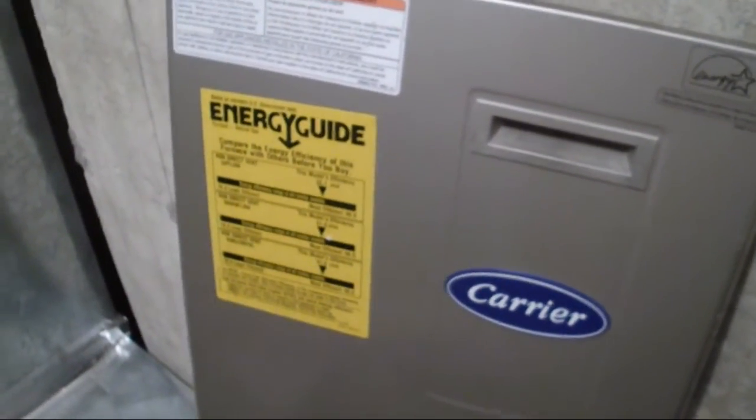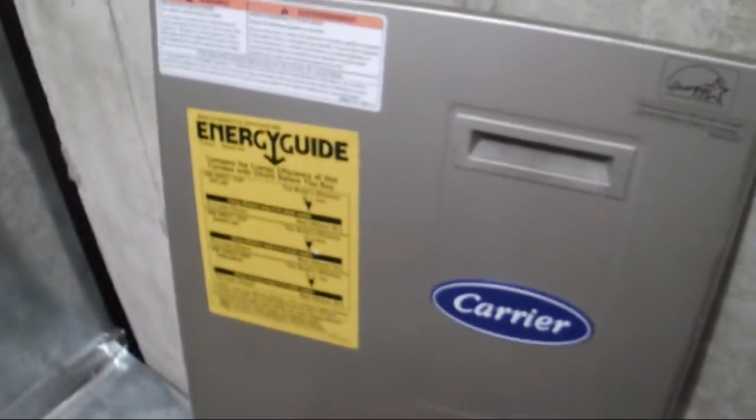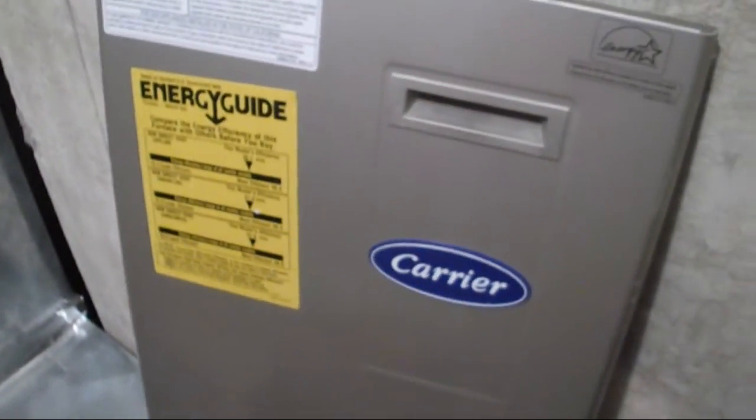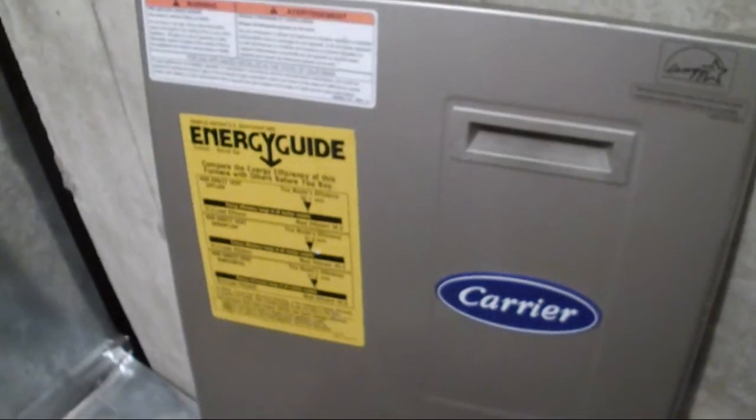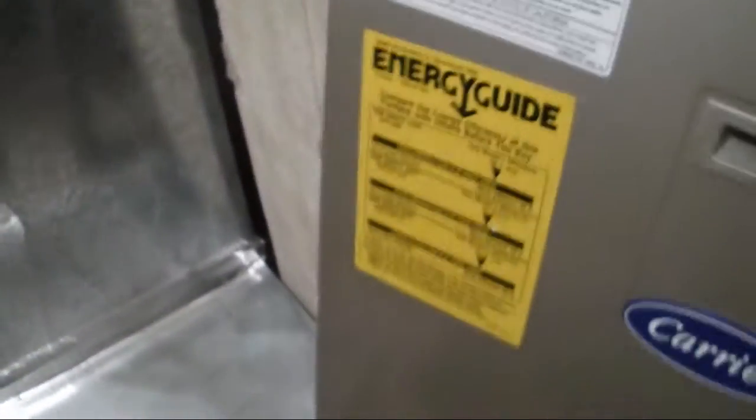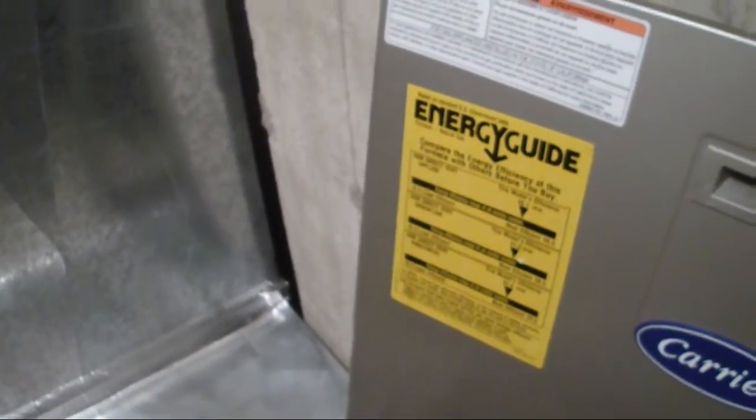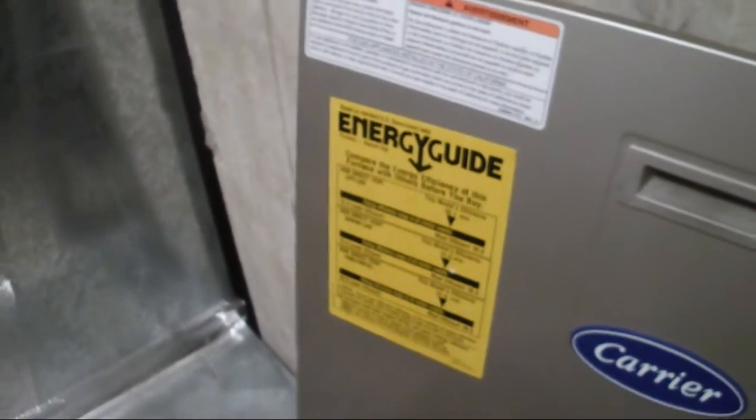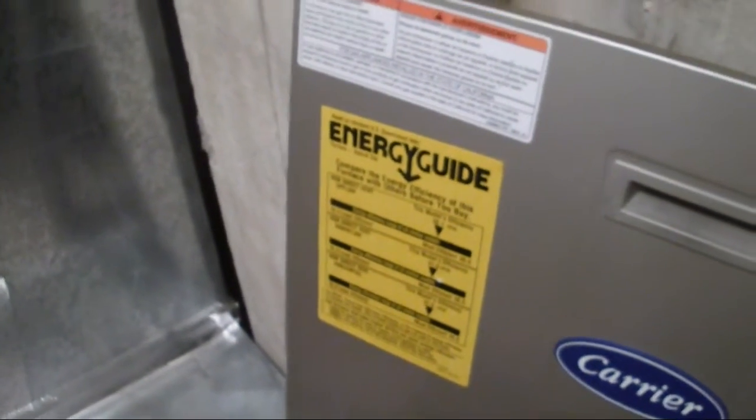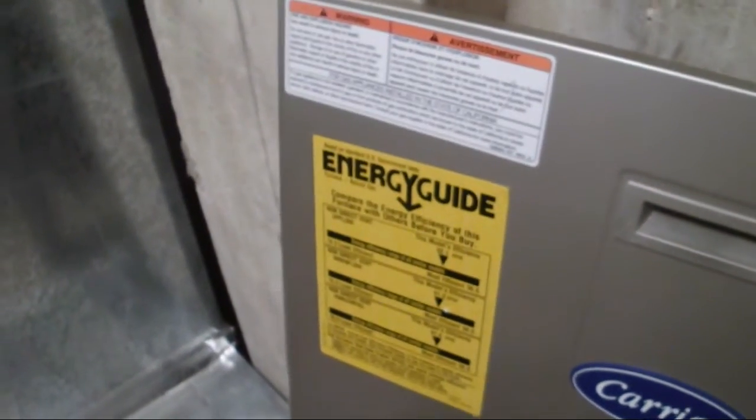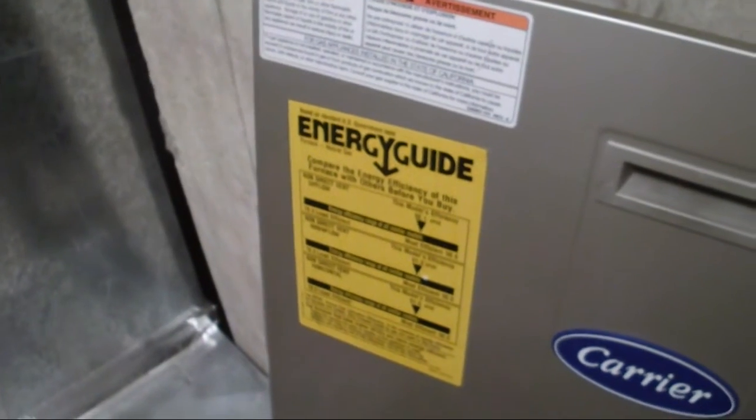Now what one of my neighbors did actually, they have a two and a half ton air conditioner for a 2,040 square foot house and they didn't think it was cooling off the second floor to their liking so they put a three ton coil and furnace in. Yeah. Well they should resize the ductwork too. A lot of times the ductwork just wouldn't be able to handle it. Because it was made for that two and a half ton.